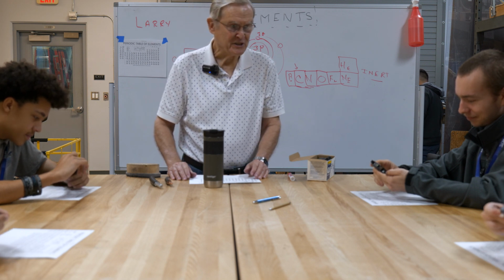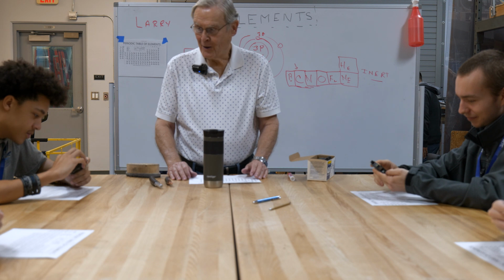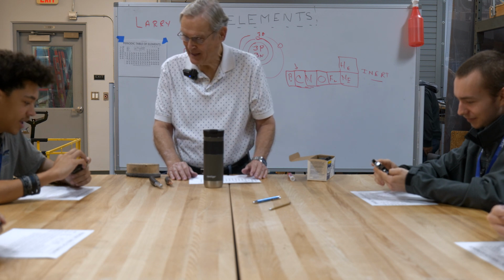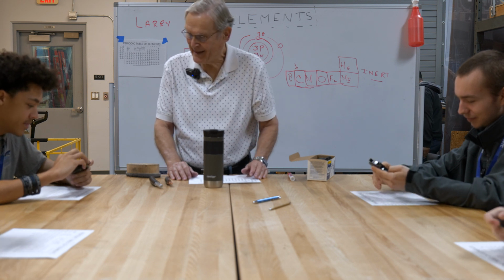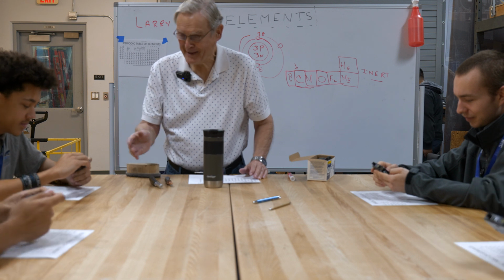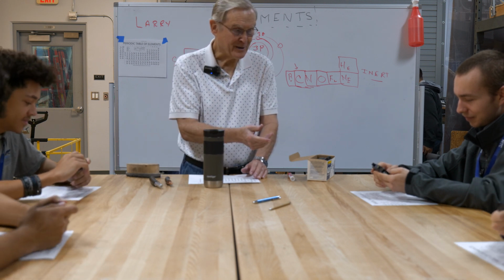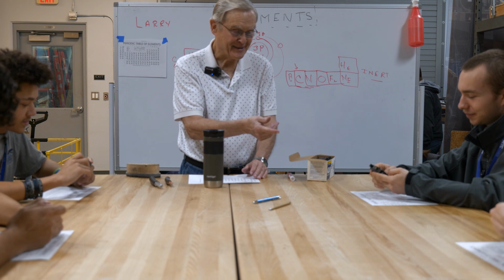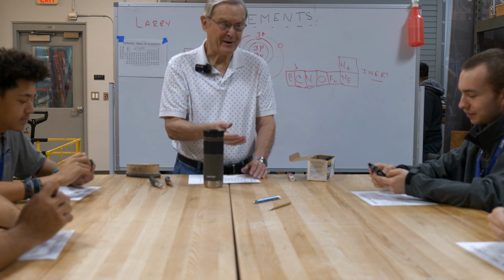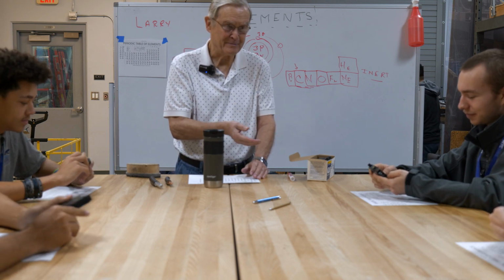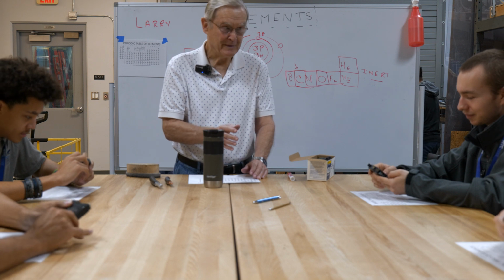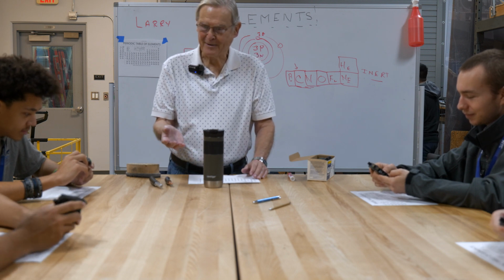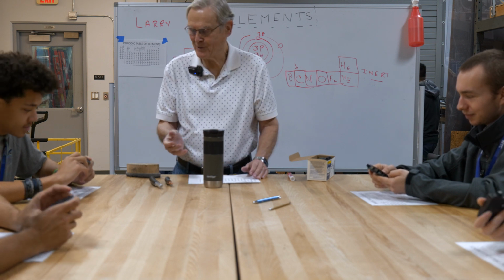Did you see anything about CU? Oh yeah. Was that AL? What is AL? Aluminum, right? Aluminum, yes. So this circuit breaker can be used on either one. It says so right on the side. Now there are some circuit breakers that say you can only use copper. You can't use aluminum.